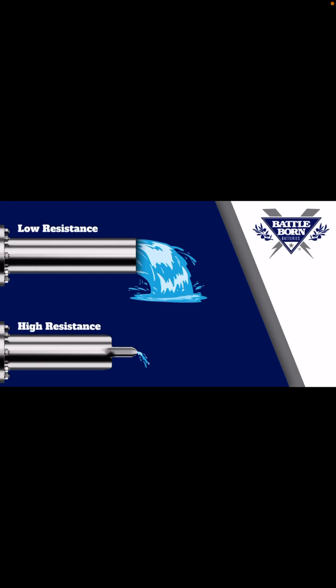Same thing if you were to put your amp clamp on that wire coming out of the breaker, you might see a drop in current. And what you're seeing is resistance. So maybe that terminal screw is loose where it's clamped onto the wire. So when you pull on it, you're creating a little gap. And now all of a sudden the electricity went from having a clear path to having to jump this gap. That would be a form of resistance.